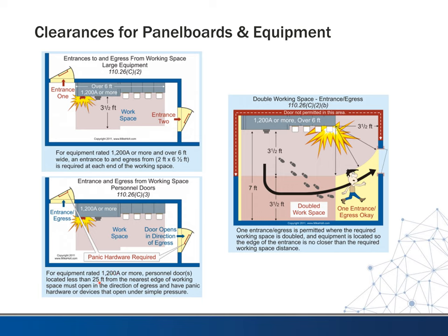If we have the same condition and the doors are less than 25 feet from the nearest edge of the clearance space, then they must open in the direction of egress and they must have panic hardware. I usually just say on my plans and inform my designers that if it's 1200 amps, six feet or more, I want that regardless of whether they're within 25 feet or not. The reason for that is if there is an incident, where something arcs or flashes or burns up and the electrician working on it gets burned and burns their hands, they can make it to the egress door and open it and get out without having to use their hands, right? So this kind of makes sense.